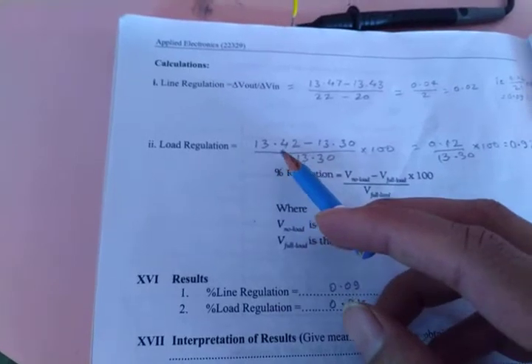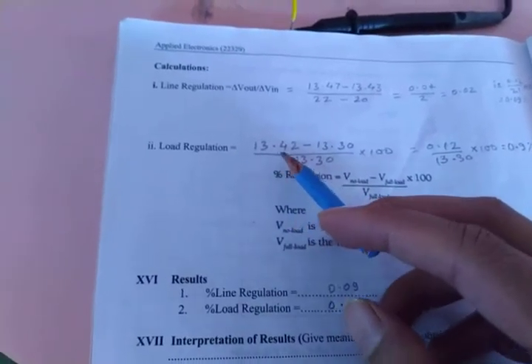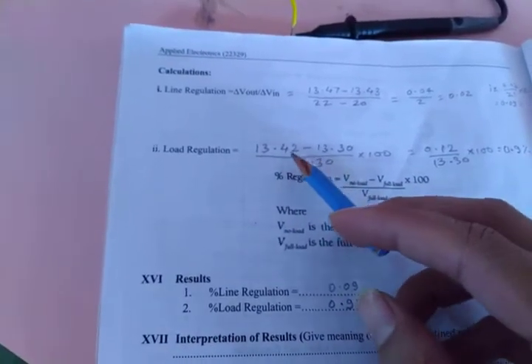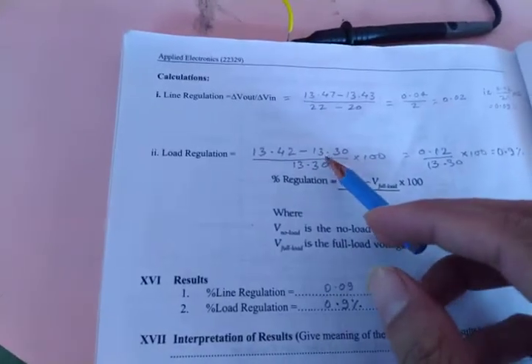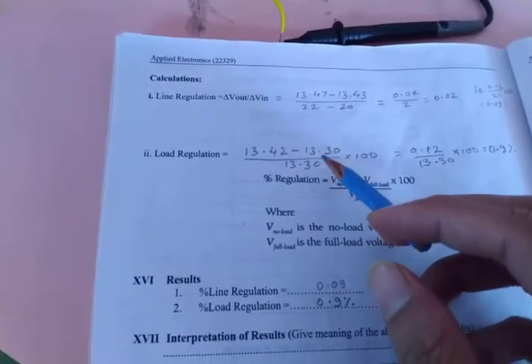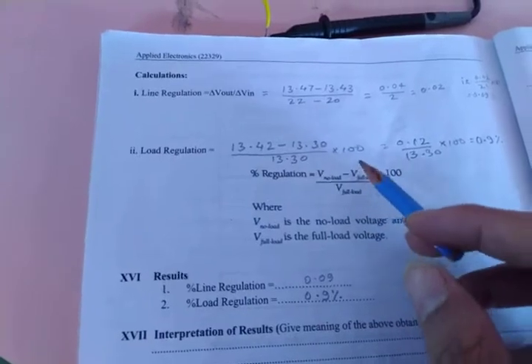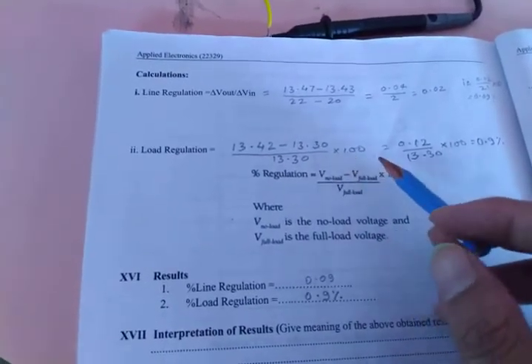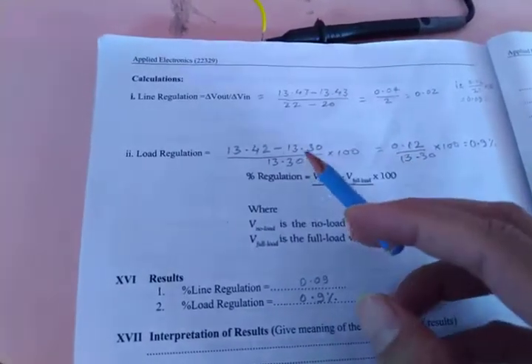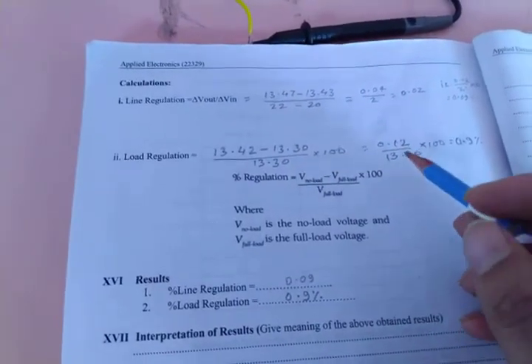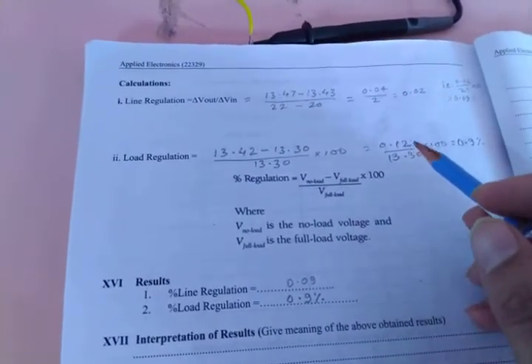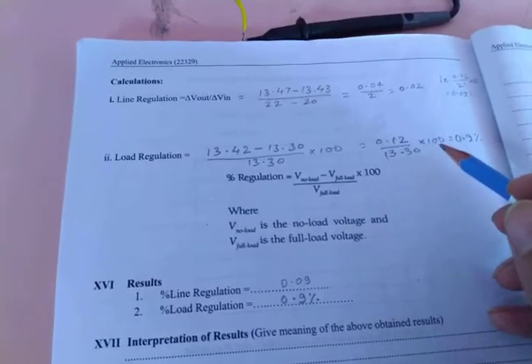We have taken two readings, that is 13.42 volt as the no load voltage and 13.30 as the full load voltage, divided by full load voltage as per the formula, multiplied with 100. Substituting the values, the difference we got was 0.12, divided by 13.30, into 100.